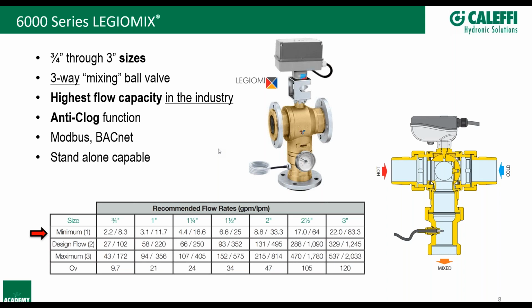We had a prison system in Florida install about 16 of these. The biggest selling point for them wasn't that it could connect to building management, or any of that other stuff, and they weren't doing thermal disinfection — they wanted the data logging. It's the funniest story, and it makes me think of how great America is: they were running into issues where inmates were suing the prison system because they were getting scalded. Now with these LegioMixes doing the data logging, they can use that information to combat those lawsuits and keep from getting sued. Wild way of doing things, but it shows it doesn't have to be just thermal disinfection — it can be used for all these other things too.